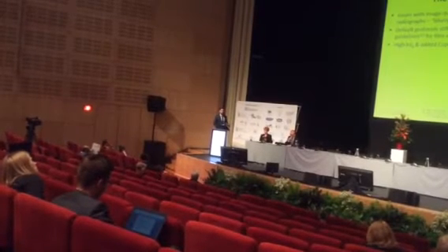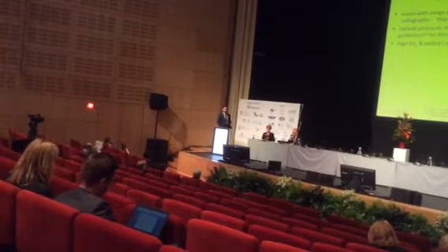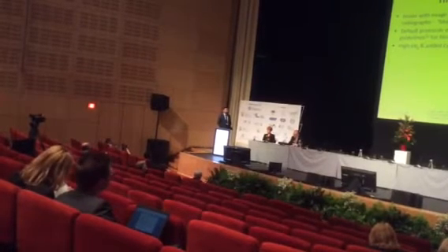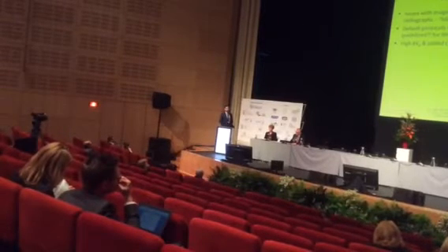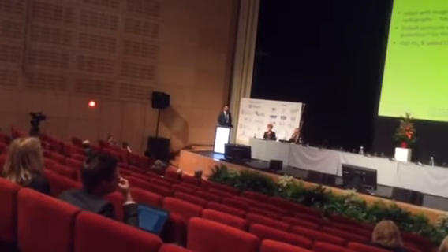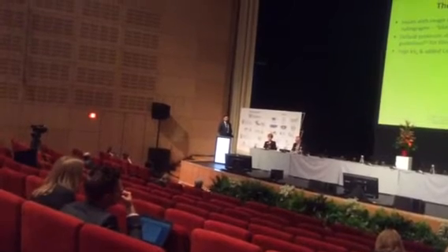cortices of the tibia and the surrounding soft tissue were leading to difficulties making confident clinical decisions. So I did a bit further work and found out that the default protocols were set based on a combination of the manufacturer's advice, previous staff experiences, and the 1996 European Commission guidelines. Now, these guidelines were published when film screen systems were still primarily being used, and they generally encouraged a higher kV and additional copper filtration for all paediatric projections.